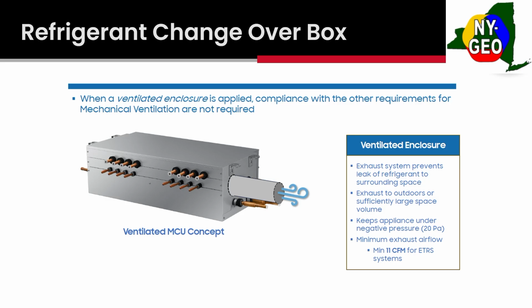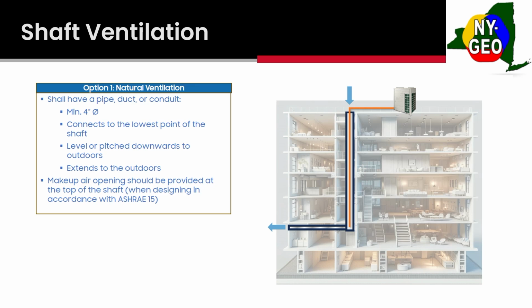So everyone's favorite topic, shaft ventilation. This has been the heartache of every multifamily contractor out there, trying to figure out how to install split systems with this new shaft ventilation system. So the shaft containment requirements: anytime refrigerant passes through 2 or more floors, the roof doesn't count. So if you go from the roof to this top floor, you don't need a shaft. As soon as you go down to the very next floor, then this all needs to be in a shaft. So that's pretty important there.